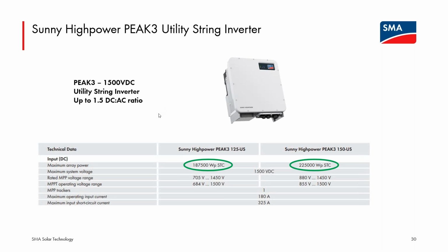And we, in fact, have just recently increased, for only the PEAK3, the full load hours that would be allowed. It is now a 3,000 full load hour limit, not 2,400 like the CORE1. That's, in essence, 8 hours every day of a whole year where it's running at full capacity. So 3,000 peak load hours is quite a bit.